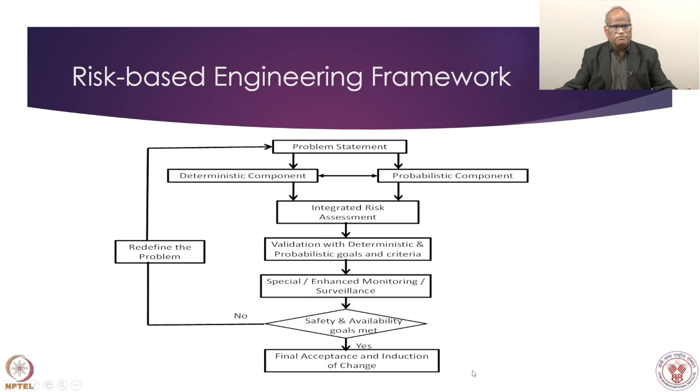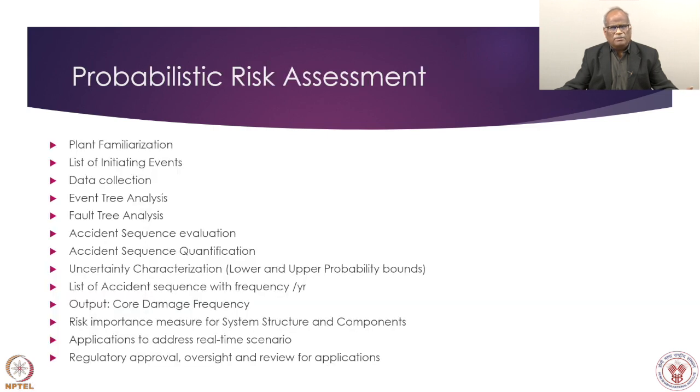So this is the risk-based engineering framework I discussed. And then how probabilistic safety assessment operates, probably we had devoted 2 weeks for this. But I'll just sum up in one slide or one and a half slide: plant familiarization, list of initiating events, then data collection, event tree analysis, fault tree analysis, even by graphics you would be able to recollect what we discussed. Then finally when we do fault tree analysis, integrate with the event tree analysis, we get accident sequences. And then once we do quantification of accident sequences, we get the core damage frequency for the plant for all the initiating events, uncertainty characterization, upper bound, lower bound, which are very important elements of PSA.